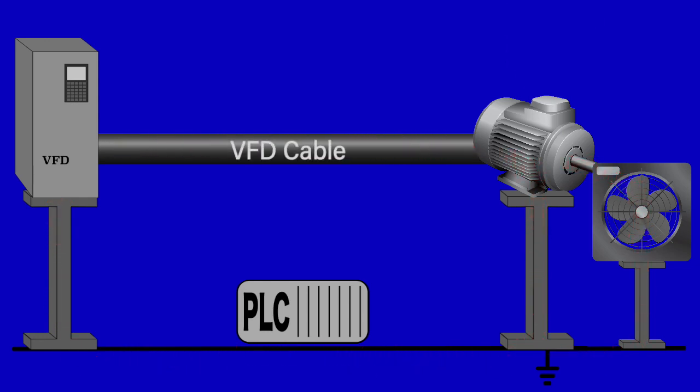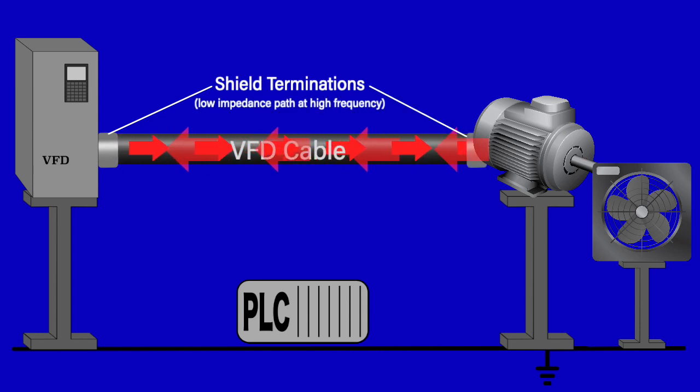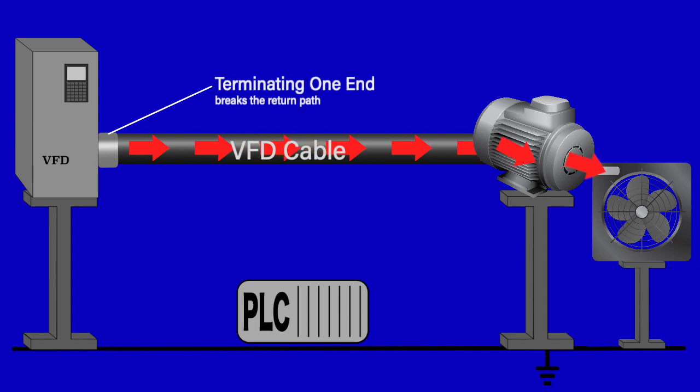VFD cable can control the path of this common mode current. The VFD cable's overall shield has a large surface area, which provides a low transfer impedance at high frequency. Terminating the shield with low impedance at high frequency terminations at both ends of the cable provides the common mode current a controlled path back to the inverter. Terminating only one end of the cable's shield breaks the path, and the common mode current is left uncontrolled.